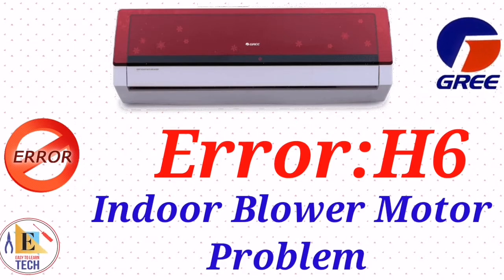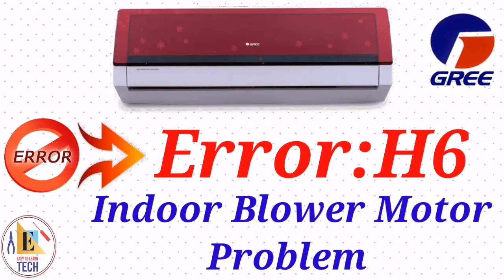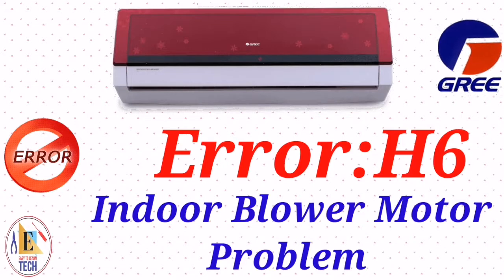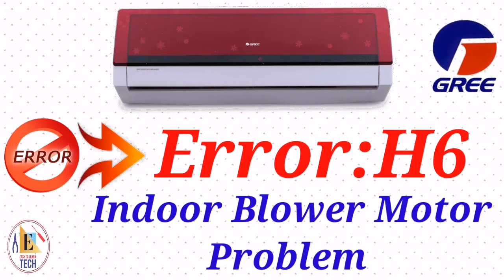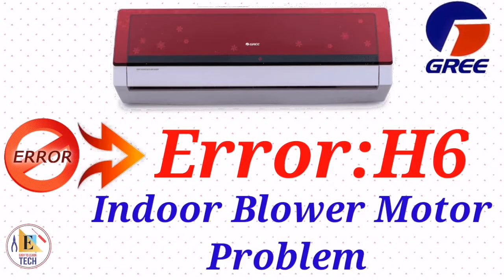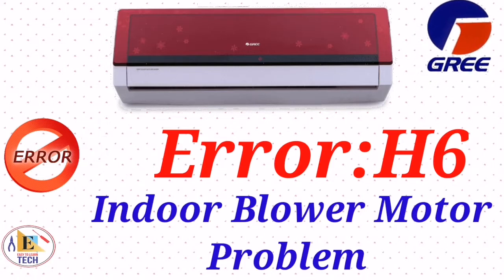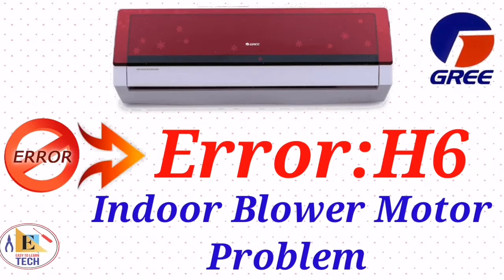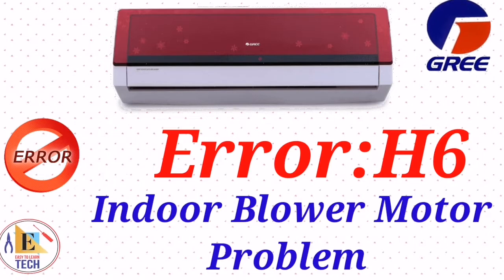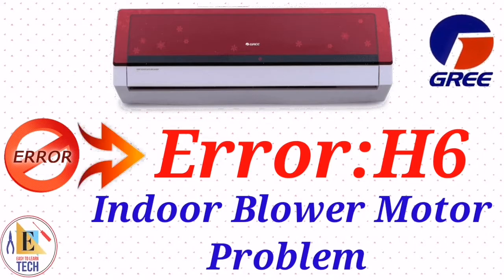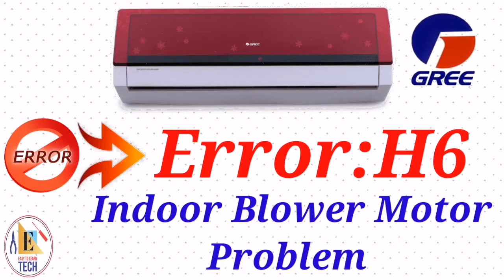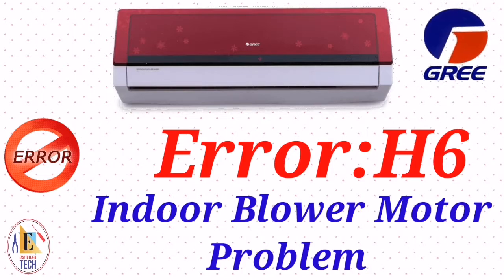And if you are getting the same error, then you have to check the resistance of our fan motor. If the resistance is not good, then you have to replace the indoor blower motor. And if the resistance is good, then you have to check the output supply of our indoor PCB, if the output supply is coming perfectly or not. If the output supply is not coming perfectly, it means our indoor PCB is faulty. You need to change the indoor PCB and you will get the solution for this error.